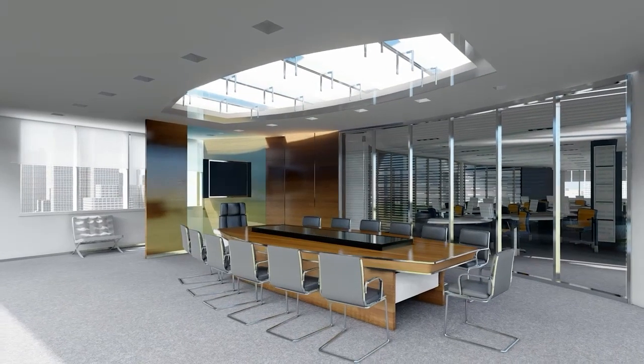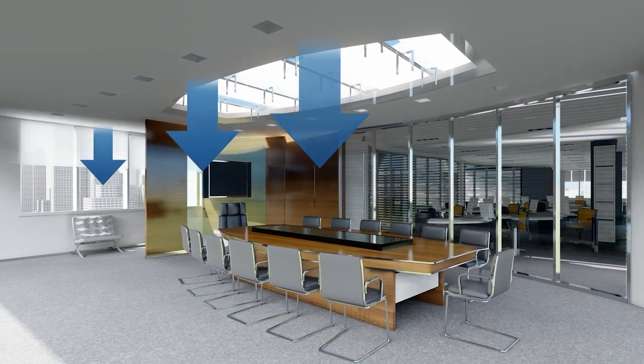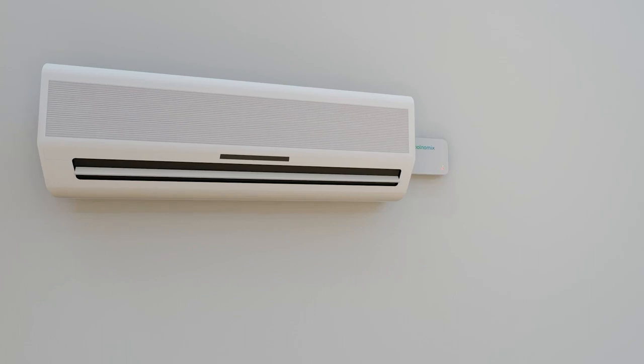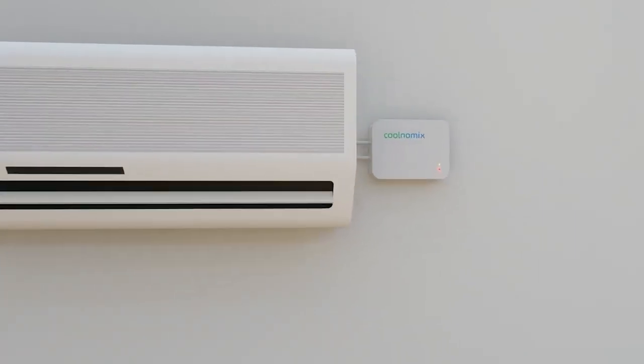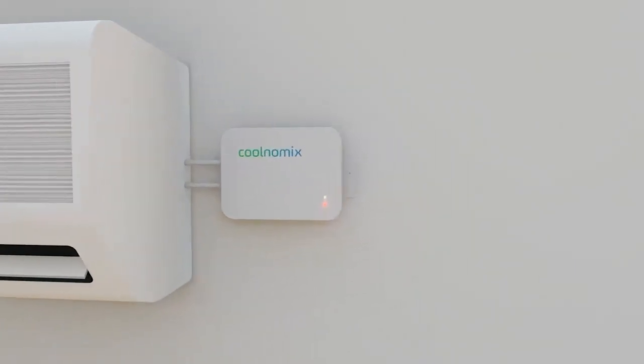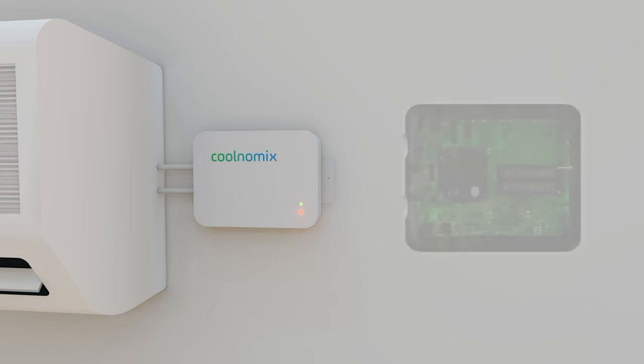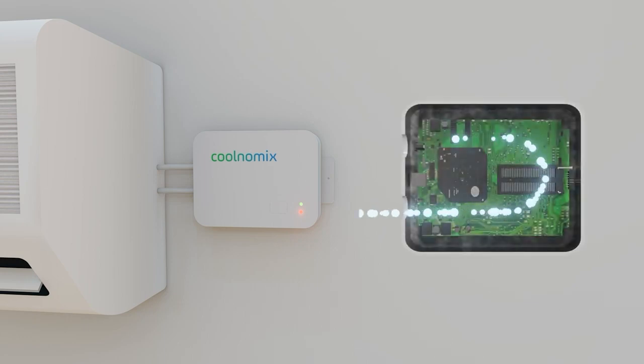Coolnomix uses a small control unit, 2 precision sensors and an electric relay. The 2 sensors are placed in the supply and returned airflows and provide feedback to the control unit. The control unit sends signals to the cooling equipment to let it know the optimal time to run, in order to minimise energy consumption without affecting the output you need.